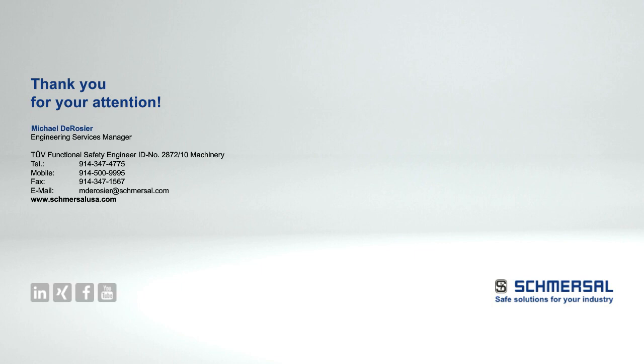What we're starting to see is that is becoming a requirement in different standards. I can pull out one specific one, the ANSI RIA 15.06. That is in two parts, and it's a mirror image of the ISO 10218 Part 1 and Part 2. So Part 1 is for the robot manufacturer, Part 2 is for the integrator. And when you look at it, one of the requirements in there is for the integrator to develop a risk assessment and perform that risk assessment. It doesn't say anything specific about SISTEMA, because SISTEMA is one tool for doing that.